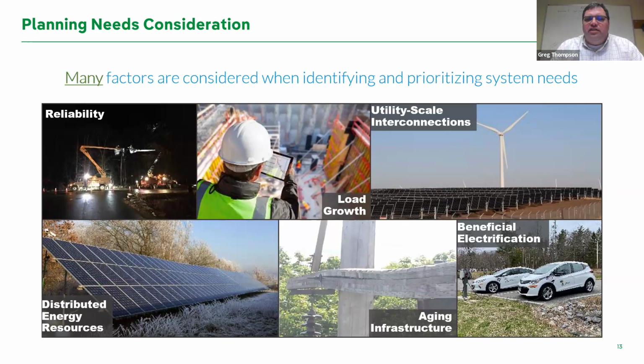When you start getting into distribution, it's less about capacity and more about ability. You start looking at two-way power flow. The system was designed 100 years ago when you only had one flow - it came from the generator through the substation to your house. Now, in amongst that, we've got distribution generation, which we've put on in the middle. So now I've got to be able to have power go through that recloser both ways and not trip them off.